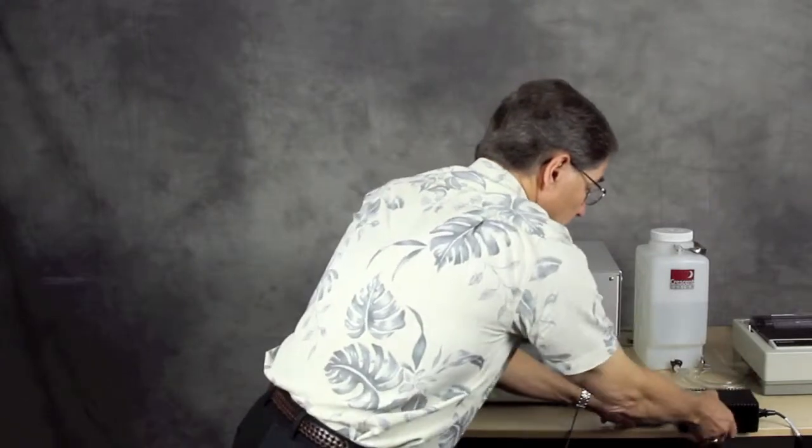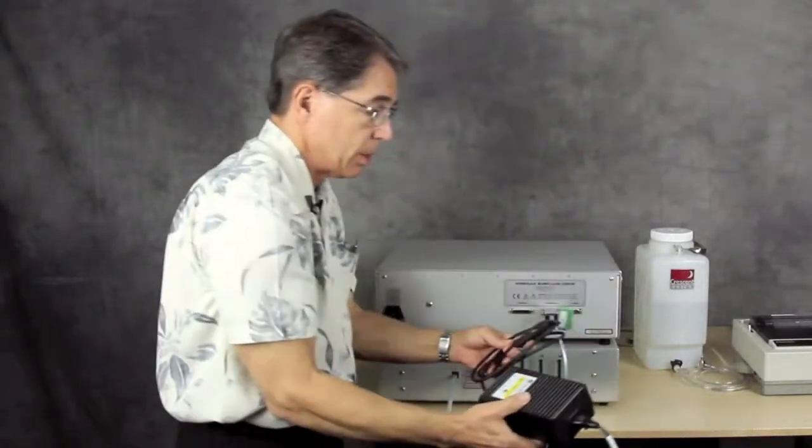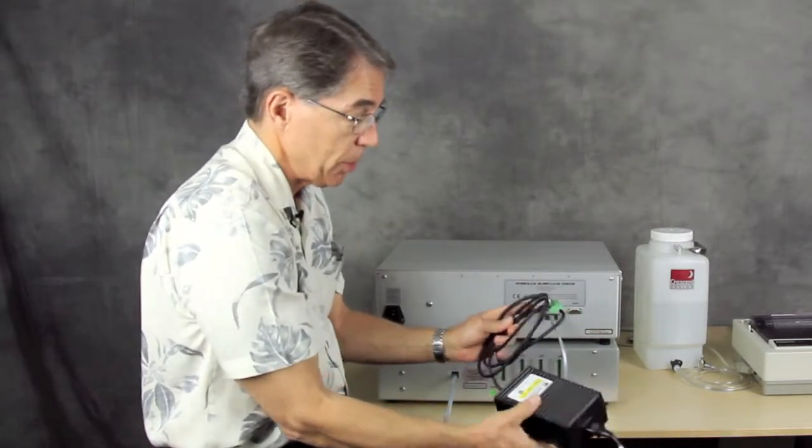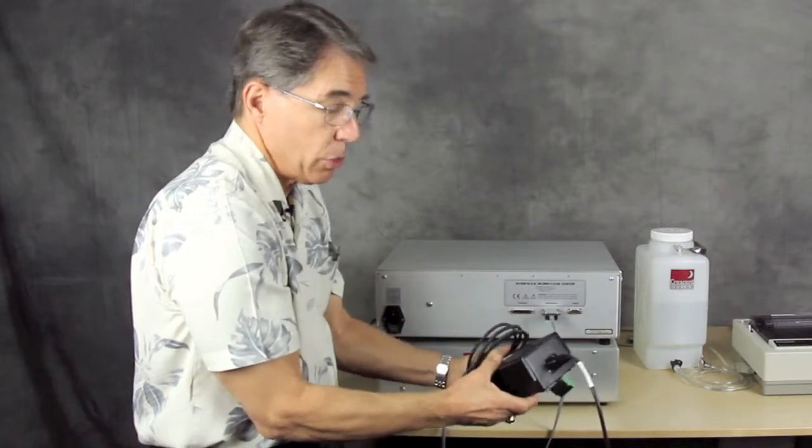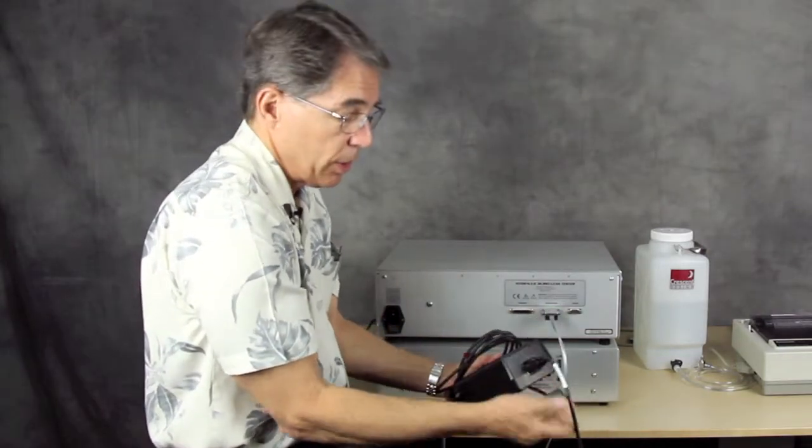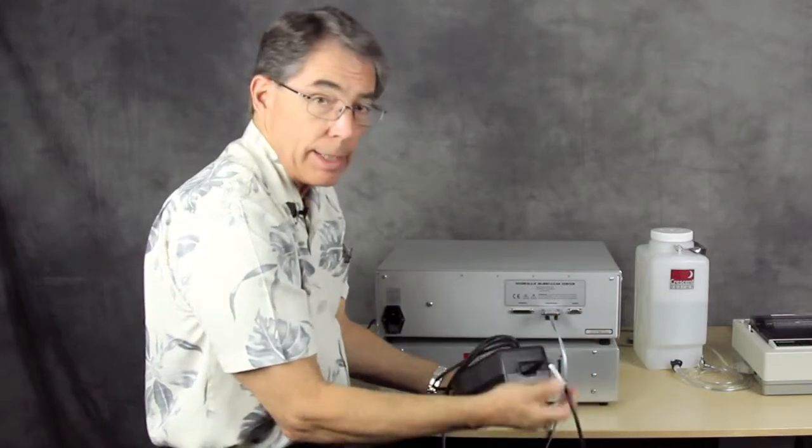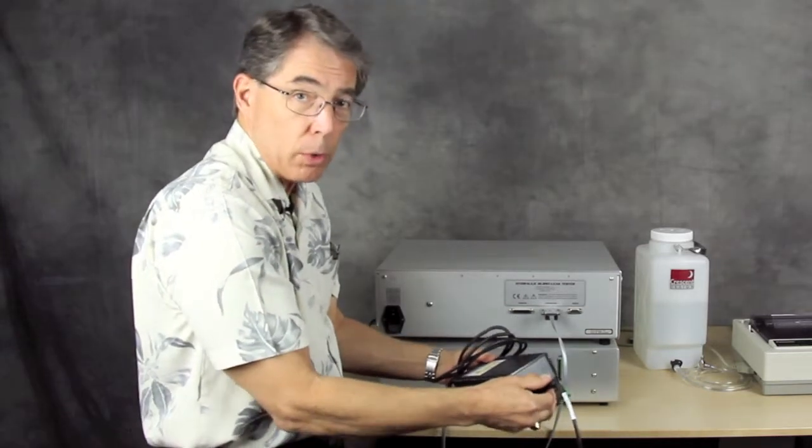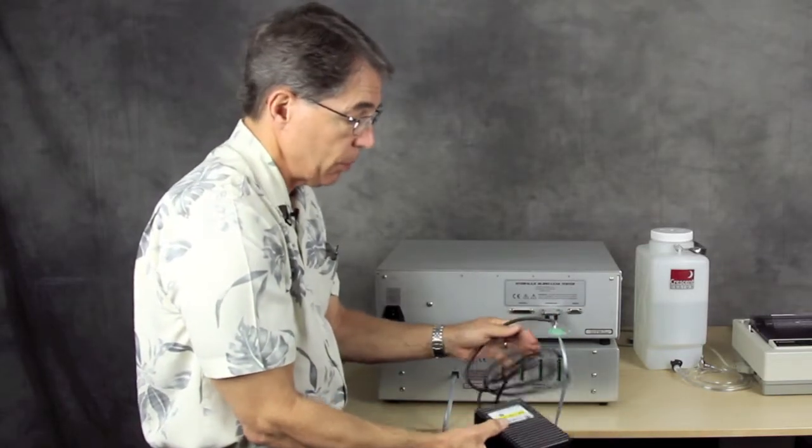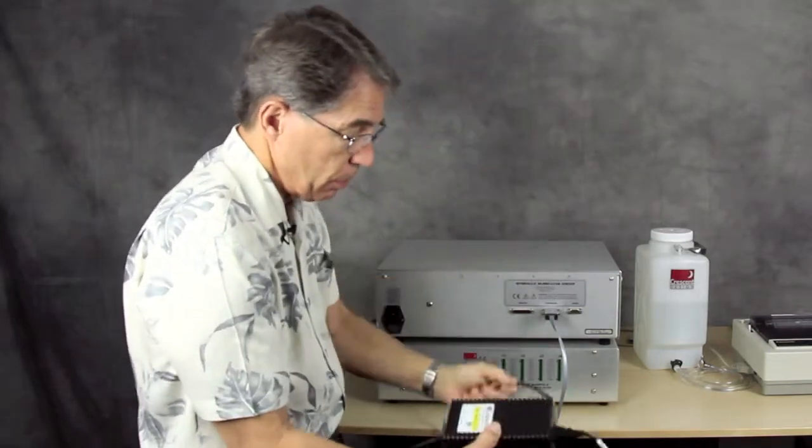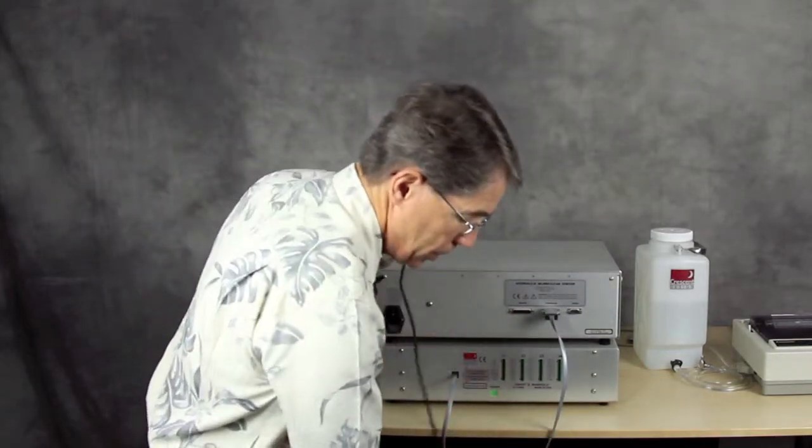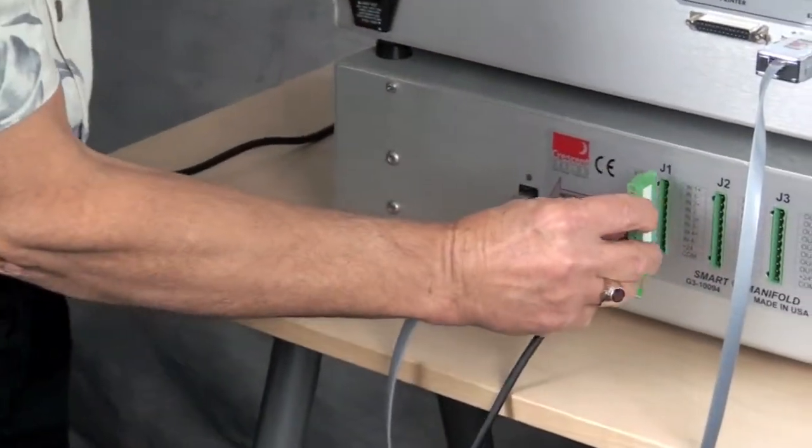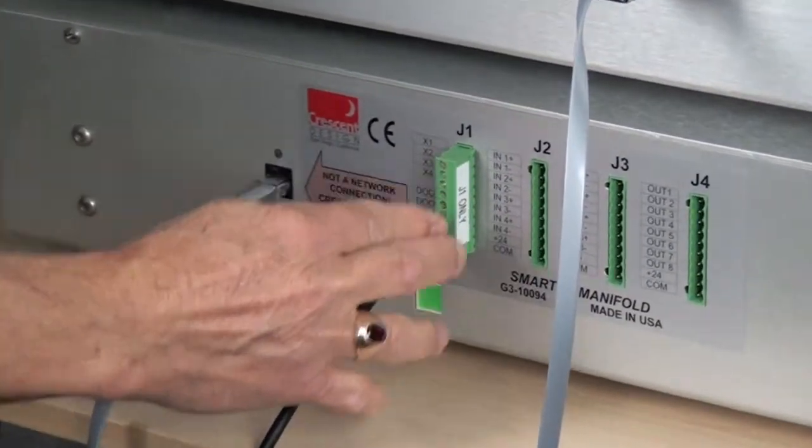Also, we have the power supply. This is the smart manifold power supply. Ours happens to be labeled for our demonstration purposes here. But this power supply is universal in that it will work anywhere in the world. And it uses a standard IEC cord, power cord. And we supply the appropriate cord for wherever it happens to be used in the world. And then there is the actual power connection to the smart manifold. And that's J1 only. And we're going to go ahead and plug that in right here.